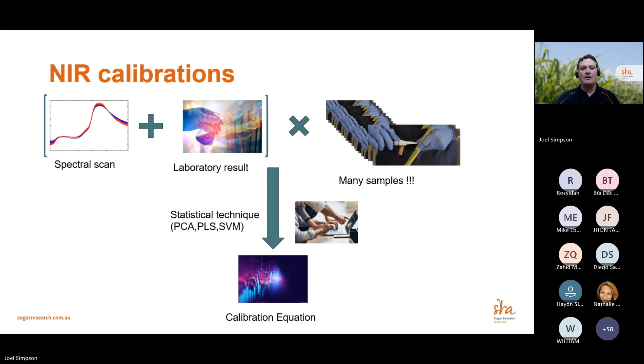So what are the advantages of this? The speed of analysis gives you opportunities with things that you couldn't do using the traditional laboratory methods. A good example would be fiber. The fiber test takes 3 hours in the traditional laboratory method. NIR scans every 7 seconds. So you wouldn't even be able to represent a consignment at that rate of 3 hours, but at 7 seconds you can see the variation within the consignment. So it's quite an advantage.